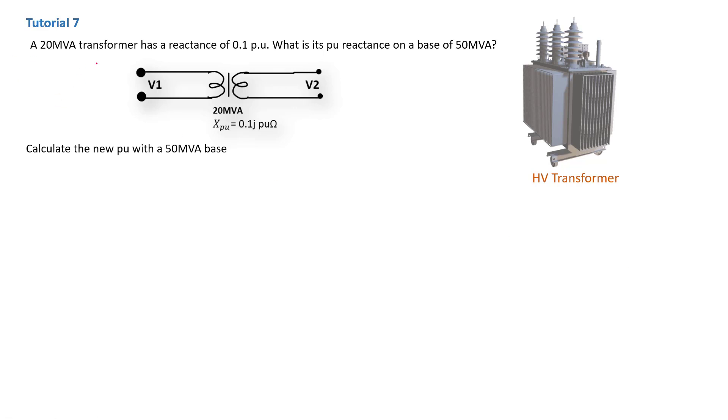In this tutorial, we have a 20 MVA transformer that has a reactance of 0.1 per unit. So that's a per unit reactance of 0.1 for the transformer in front of us. Now they're asking us what is its per unit reactance on a base of 50 MVA. So in this case, the 0.1 per unit reactance was calculated using the 20 MVA base.